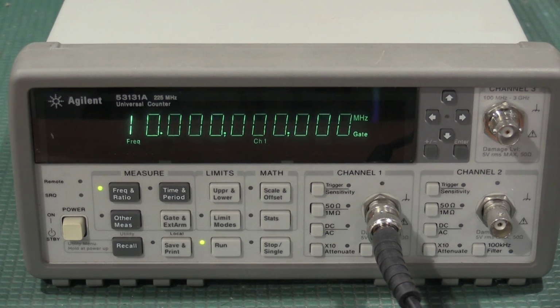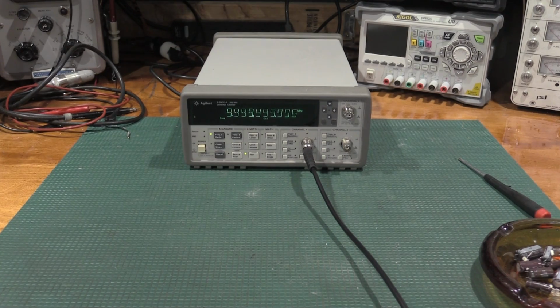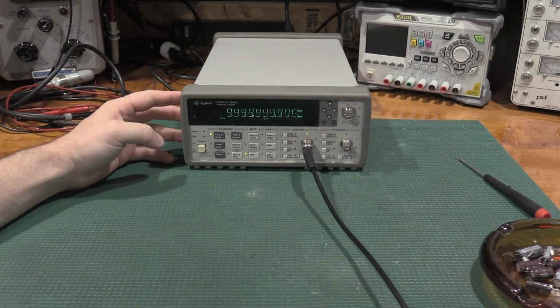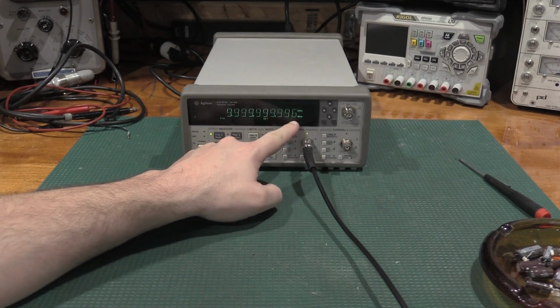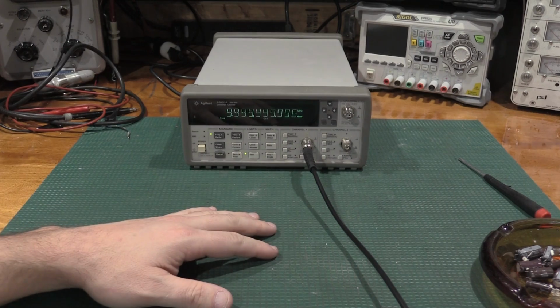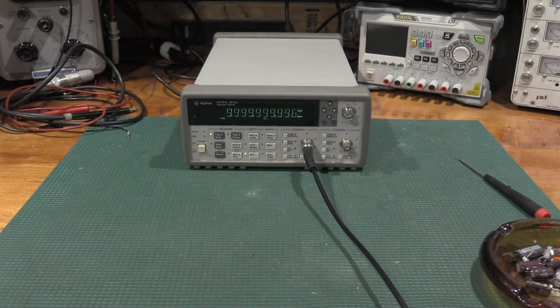So we've redefined what 10 megahertz is for this particular unit. I did not have to adjust the pot on the side of the high stability time base, and you shouldn't. So the oscillator inside is electrically driven based off of that calibration procedure. So the pot that's on the time base, you could dial a perfect 10 megahertz, but then it will fail a time base cal. So because this was set correctly, everything's good to go. It just goes to show how sensitive some of these oscillators are. The quick power off to put the bumpers back on, it danced around a little bit before it came back and settled. So it should settle back around 10 megahertz, but it's going to take a while to get there for the warm-up.